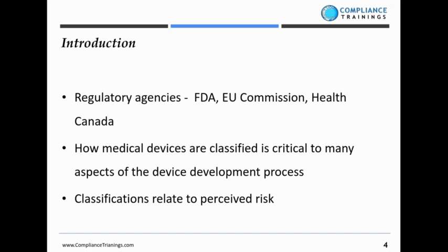Each global agency has defined several different classifications for medical devices. They all essentially have their own nuance or their own way of doing it. In general, the classifications are related to the perceived risk that the device or devices pose to the patient population. There's good news here, and that good news certainly is that there are many similarities that we can generalize upon in terms of how medical devices are classified across the globe.